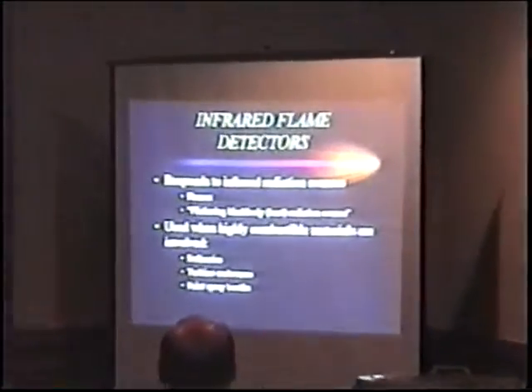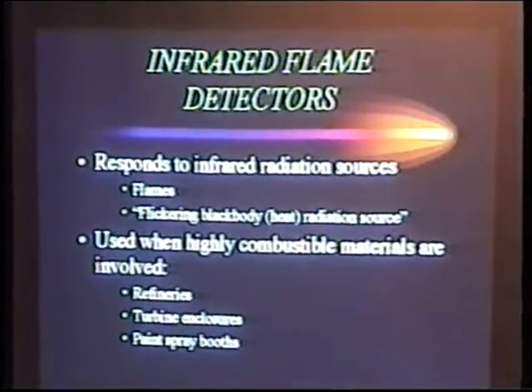These flame detectors all tend to be site-specific. You want to look at a specific process, a specific item. Let's say they're looking at a process on a refinery, and next to it we have a big boiler producing lots of heat. Maybe a fan or something gets in the way of this heat-producing item and generates a flicker or motion in front of it. IR detectors can pick that up and go into alarm, which would satisfy the requirement for that detector. Refineries, turbine enclosures, and paint spray booths are all common areas where we use infrared flame detection.